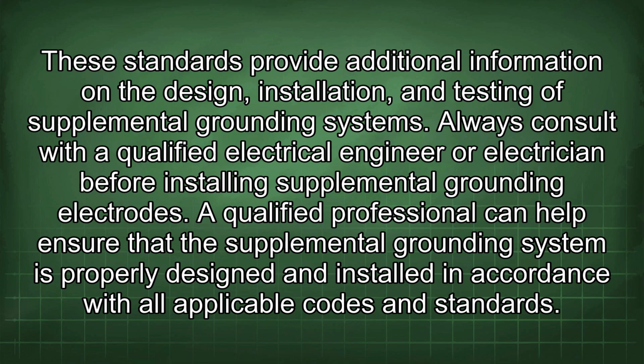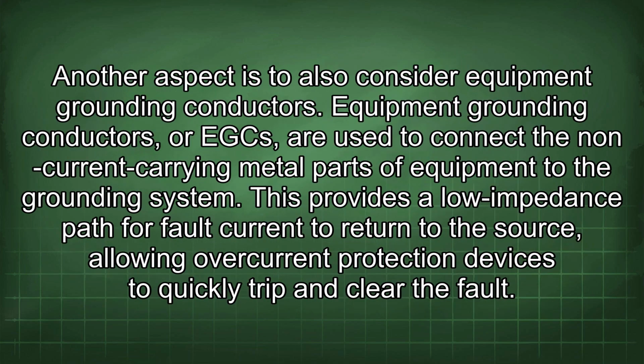A qualified professional can help ensure that the supplemental grounding system is properly designed and installed in accordance with all applicable codes and standards. Another aspect is to also consider equipment grounding conductors. Equipment grounding conductors, or EGCs, are used to connect the non-current carrying metal parts of equipment to the grounding system. This provides a low impedance path for fault current to return to the source, allowing overcurrent protection devices to quickly trip and clear the faults.